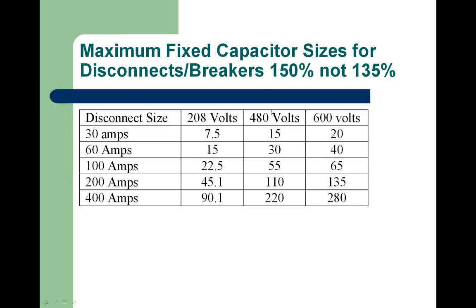And this table down here gives you an example: we can put 40 kVAR on a 60 amp disconnect. A 200 amp disconnect is a good example, because we would recommend 135 kVAR, whereas the code allows you to put in 150. If you put 150 kVAR on a 200 amp disconnect at 600 volts, you would find the conduit was warm to the touch, and in some cases you're increasing your I2R losses.